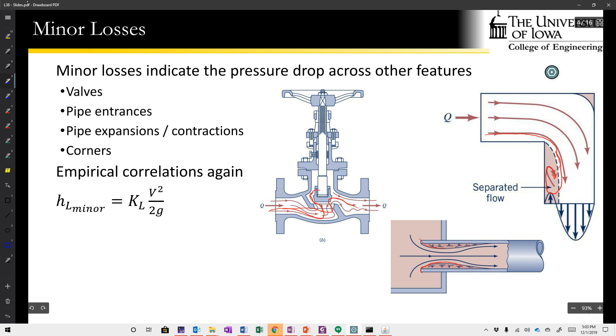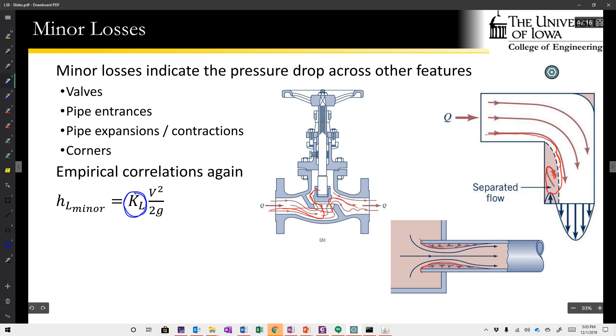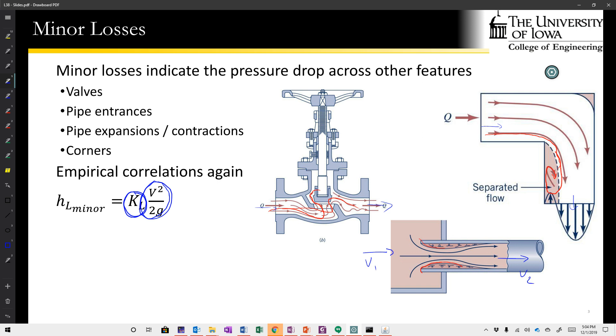Minor losses are calculated using K_L terms, which are turned into minor head losses by multiplying by V squared over 2g. You need to be careful about which velocity you use. For a corner or valve, you use the mean velocity before or after. For an expansion or contraction, you have one velocity coming in and another going out, and the tables or figures used to look up K_L values will specify whether to use v1 or v2.